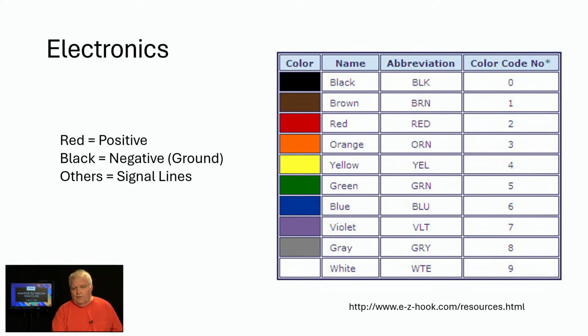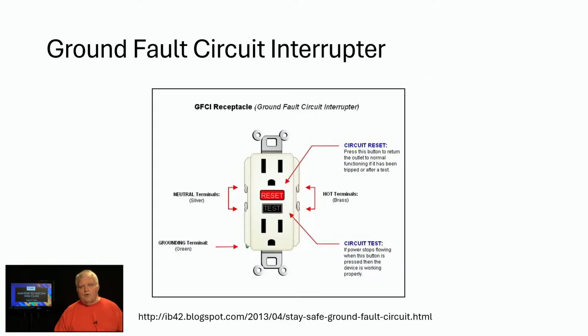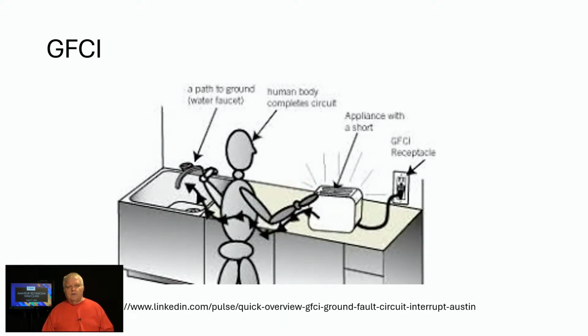We also have specialized outlets called ground fault circuit interrupters. They measure the current flowing through the black wire out to the load, and the current coming back on the white or neutral lead. Those should be exactly equal. If they're not, the GFCI knows current is going someplace it shouldn't, like through you to the ground on your kitchen sink if you've got your hands on the toaster. When it senses that imbalance, it immediately trips the circuit.